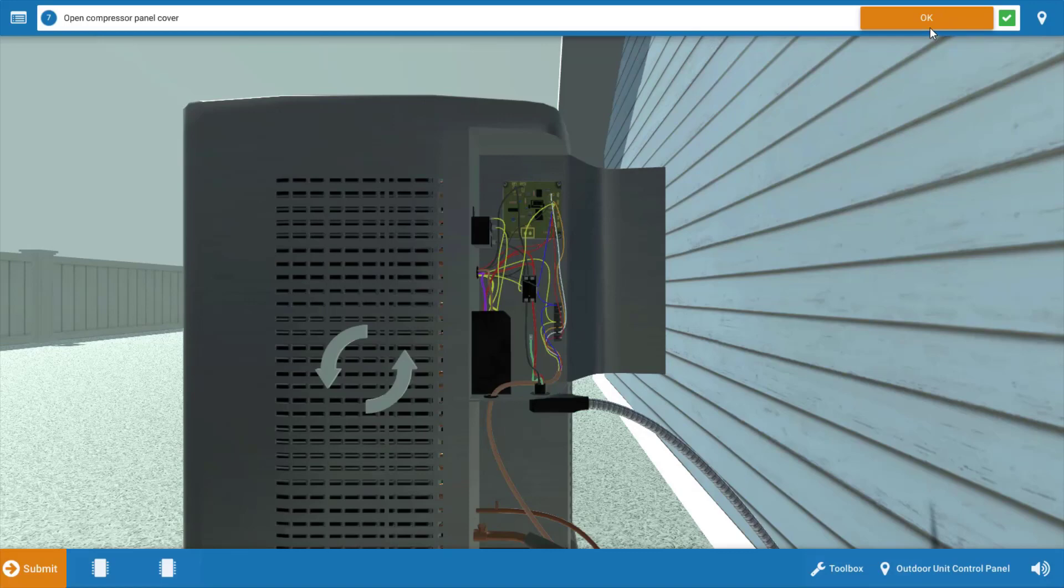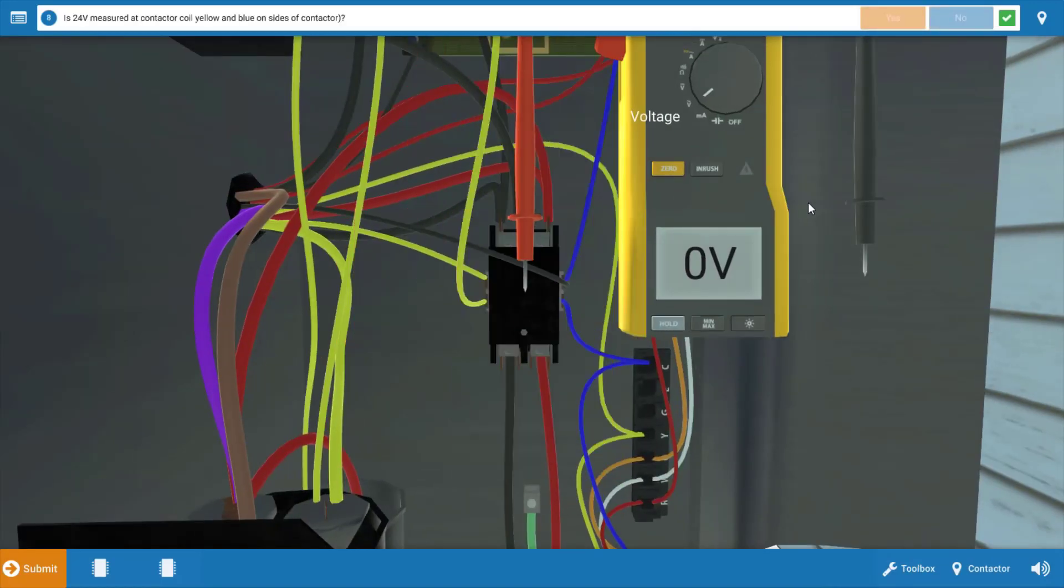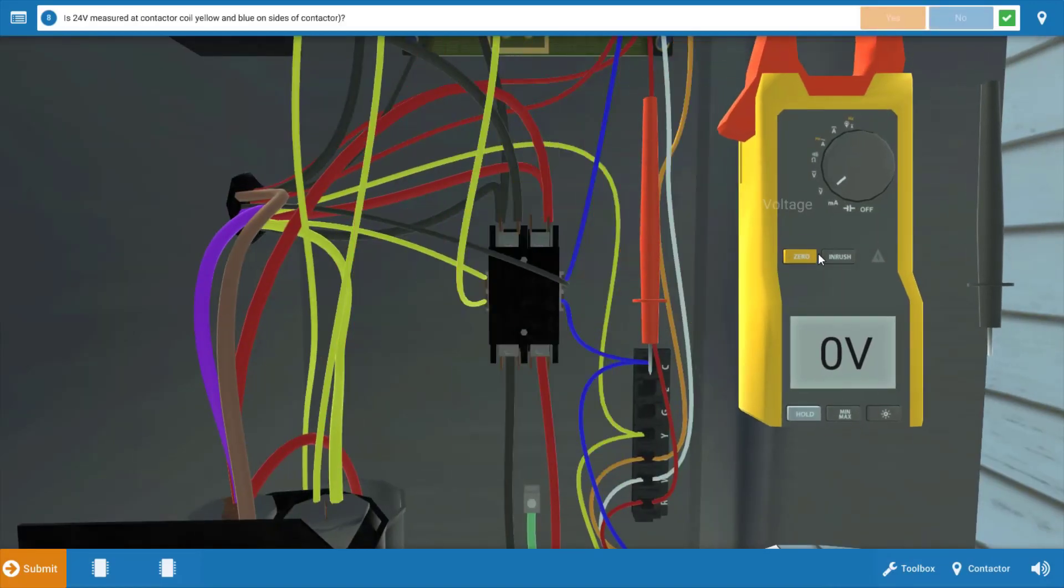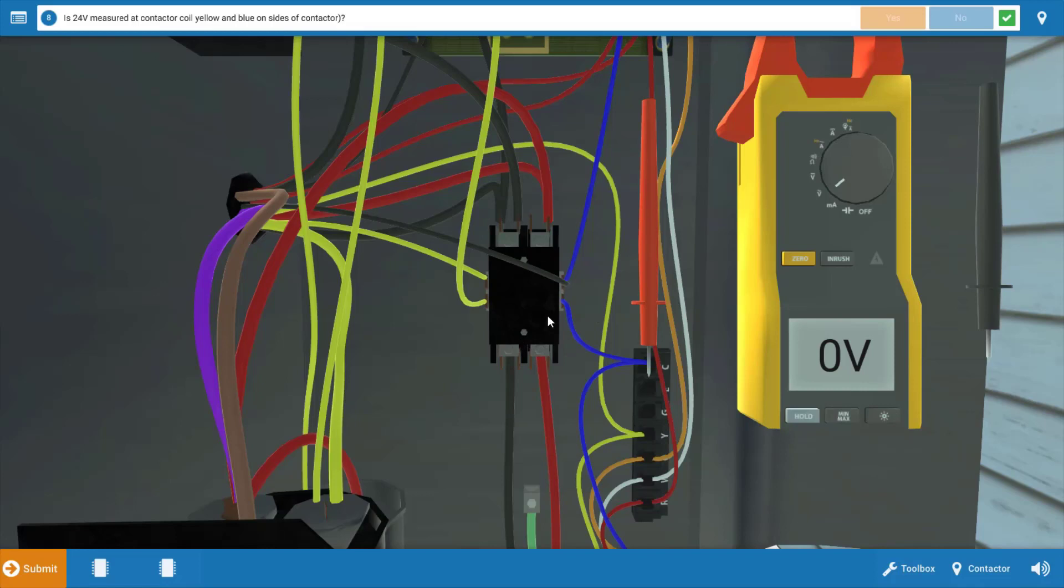Click OK on the procedure guide and we're going to take some voltage readings. But before we do that, we're going to pull out the wiring diagram and determine which components could be at fault here. Now, before we do that, here's the contactor right here in the center. It's got a coil in the base and two sets of normally open contacts. So let's take a look at the wiring diagram.